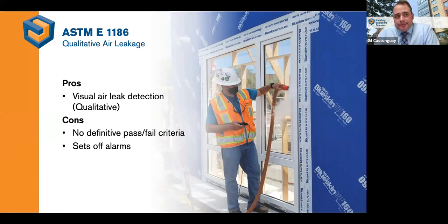The big one is the smoke does set off fire alarms. We found that out on a project. So if you're going to run ASTM E1186 with theatrical smoke, make sure as part of your planning that, number one, people understand the test and what goes into it. Number two, notify people in the surrounding area. Contractors have come up and asked if the building is on fire, and people start scrambling. No, the building's not on fire. So maybe post something saying testing is going on with smoke effects, harmless theatrical smoke, just so they're aware. Lastly, it may take going as far as notifying the fire department.